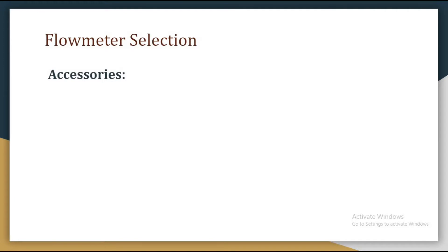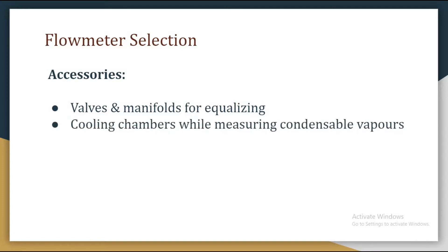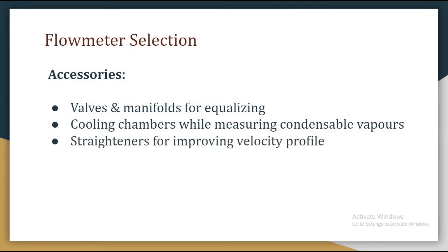The next thing is accessories. We need valves and manifolds for equalizing, and cooling chambers for a flow meter while measuring condensable vapors. We need straighteners for improving the velocity profile — when the flow profile is turbulent and not desirable, we use a straightener to restore a more linear nature. We also need separators, which prevent contaminating fluids like water in oil from entering the flow meter.